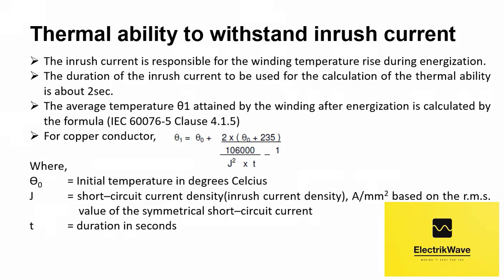The inrush current is responsible for the winding temperature rise during energization. The duration of the inrush current to be used for the calculation of the thermal ability is about 2 seconds. The average temperature theta_1 attained by the winding after energization is calculated by the formula as per IEC 60076-5 clause 4.1.5. For copper conductor, the formula is given here.